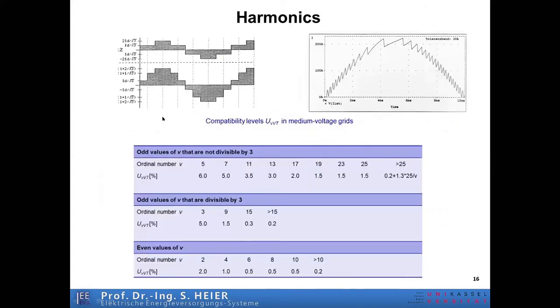So, the harmonics have been a very large problem until the 1990s. But since 94, we come up with the IGBT inverters, here and here, and then we can integrate these inverter systems in wind turbines. Here you see this tolerance band control system, and when you have a small filter behind, then you have a nearly exact sinus form, and so it is no longer a large problem to integrate very large power in the grid, and the harmonics are no longer so important.